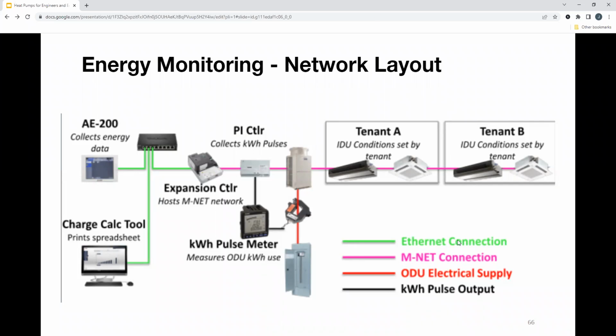But looking at right here, we have your VRF, built-in communication wiring. So in this case, we're talking about tenants. So we have tenant A, tenant B, all connected to one condensing unit, right? And then there is this PI controller, which is your pulse input controller that's connected to a central controller, right? So on an energy side, we have your red line right here. That is your outdoor unit electrical supply.